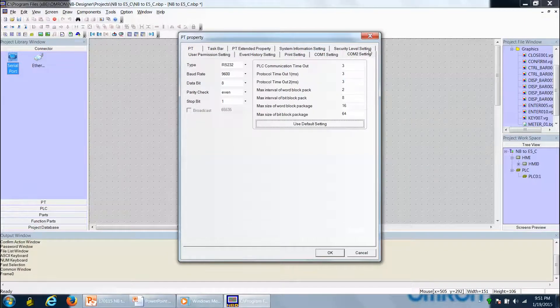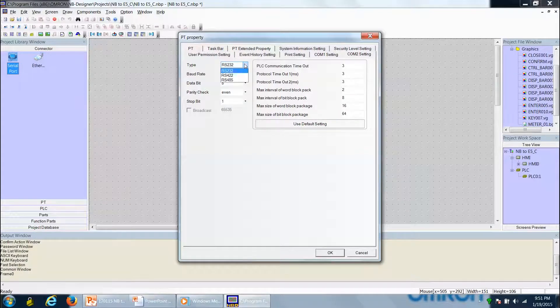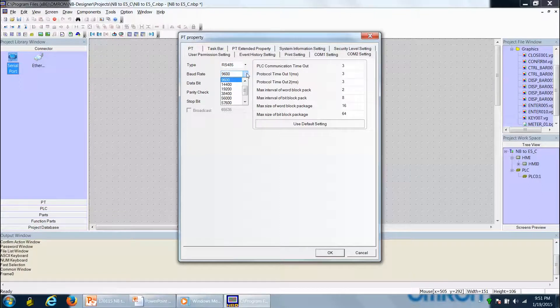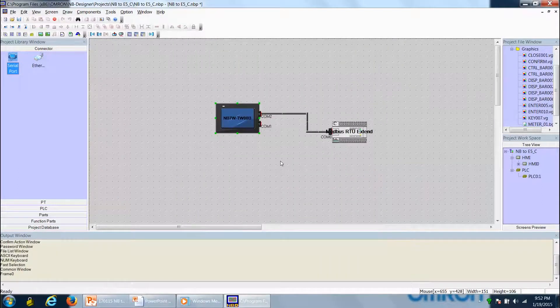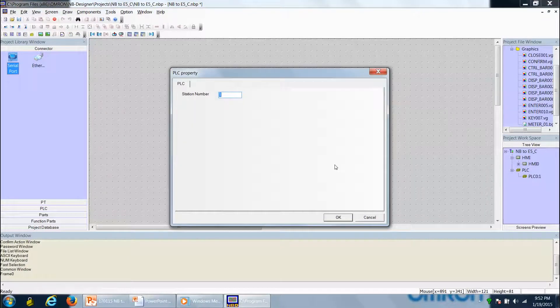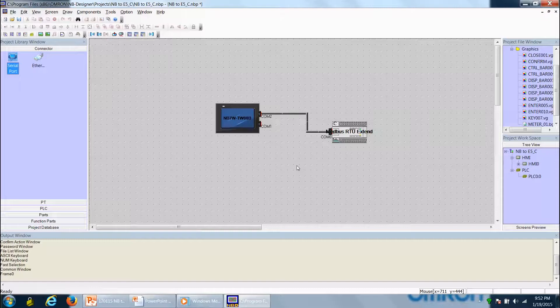Now we double click on the touchscreen to bring up the PT property window and go to the COM2 setting tab. This is where we define how communications will work coming out of COM2. We're using RS-485, so we select RS-485 from the type pulldown. The baud rate will be the default 9600, data bits remain at 8, parity will be even, and stop bits remain at 1. We click OK. We can also double click on the PLC properties and call it station number 0 — that's just a name and has nothing to do with the actual unit number.